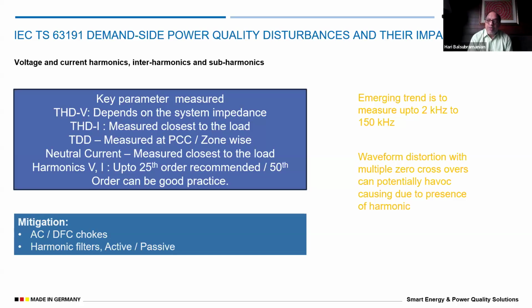Very important thing which I wanted to tell here. If someone says I have THD in my device, the next question we need to ask is, up to how many orders of harmonics do you consider for calculating THD. This is very, very important. A device can measure only up to the 10th order of harmonics and still give THD. A device can measure up to the 50th order, and still for THD they calculate only up to the 10th harmonic. There are devices like this. That's why we need a very clear understanding of the device, multifunction meters, or PQI or PMD devices in this case, to understand how they calculate THD, THDI and TDD as well. This is very important.